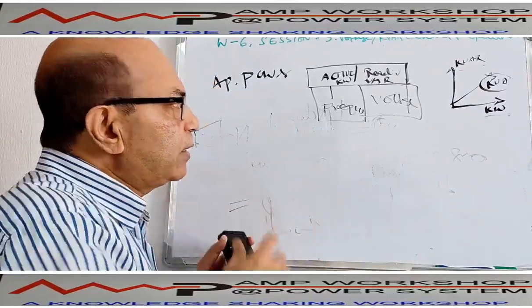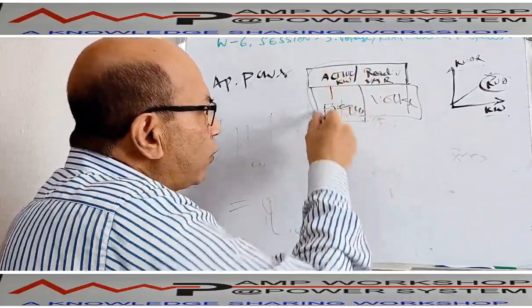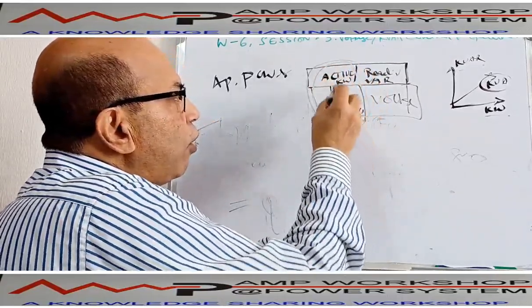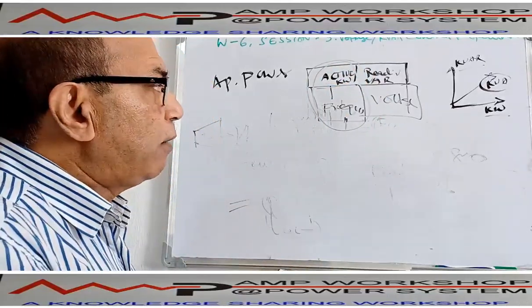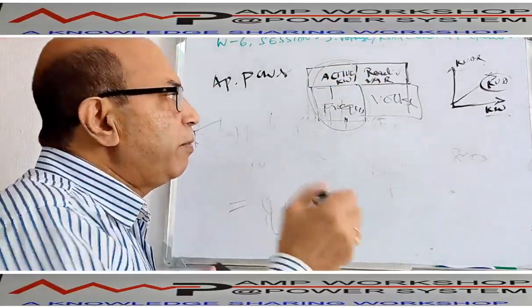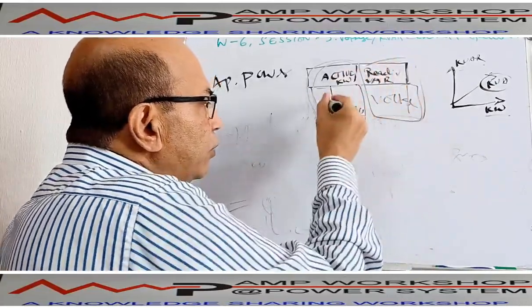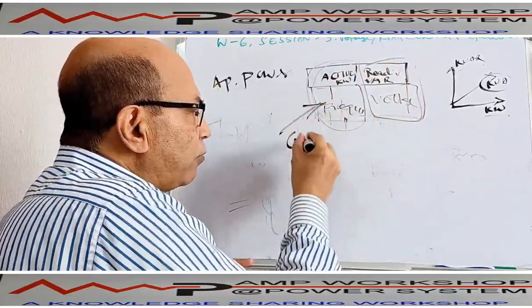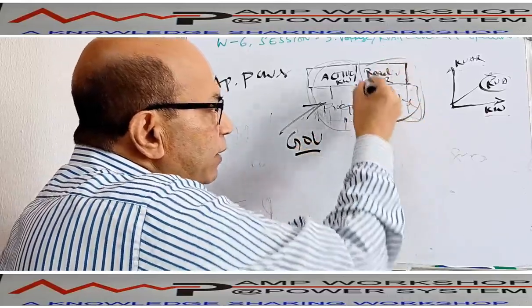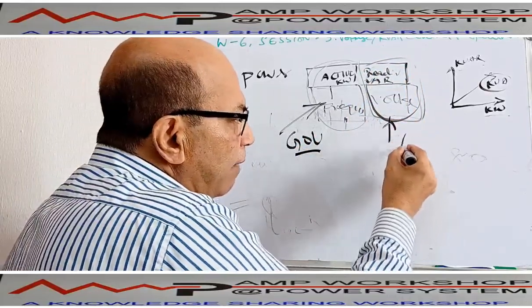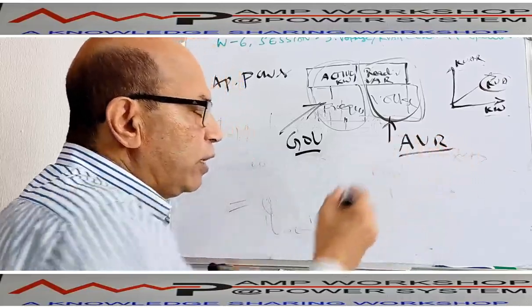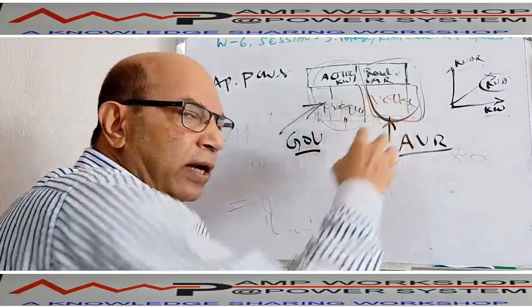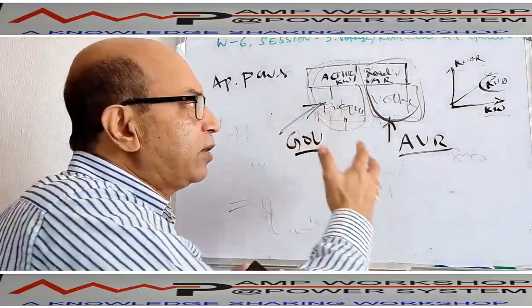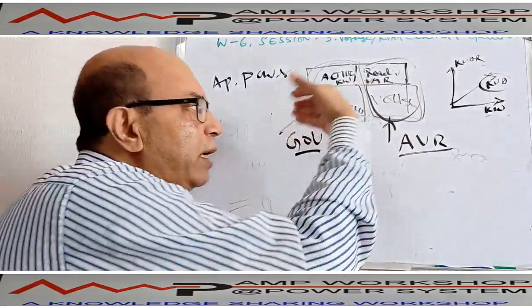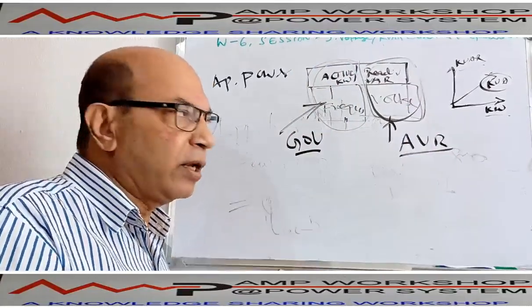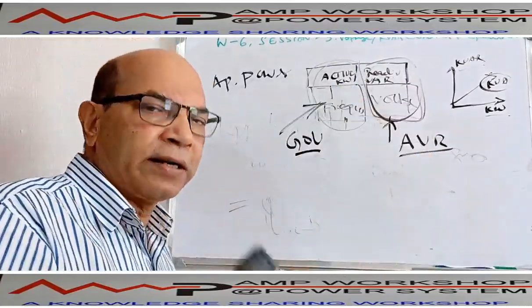That's simple. So this is one part of control. When we control the frequency, automatically we can control the active power. And when we control the voltage, then immediately we can control the reactive power. The first part we have already discussed: we do it by the governor. The part we will discuss today we do by the AVR, the automatic voltage regulator. Using the automatic voltage regulator, we can control the generator output voltage, and at the same time, if we control the generator output voltage, the reactive power will also be controlled. So this is the basic of reactive power control.